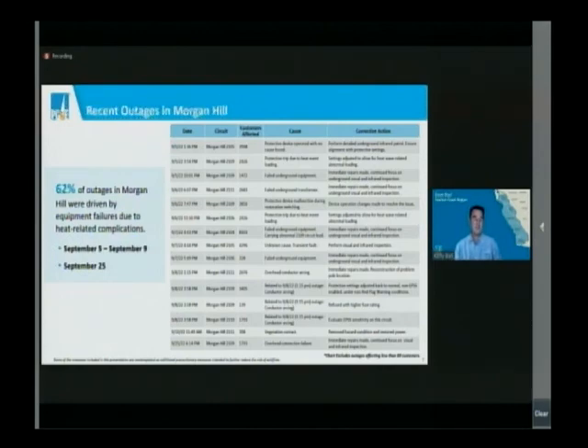The temperature didn't let up or cool down, and our system acted as it should have and opened the circuit, discontinuing power so there wasn't an imminent catastrophic failure of equipment. It acted as it was designed to. We restored power to as many people as we could quickly, which is why you see the large number of customers here. Subsequently, we had to replace all of that equipment very quickly and get everybody back in power.